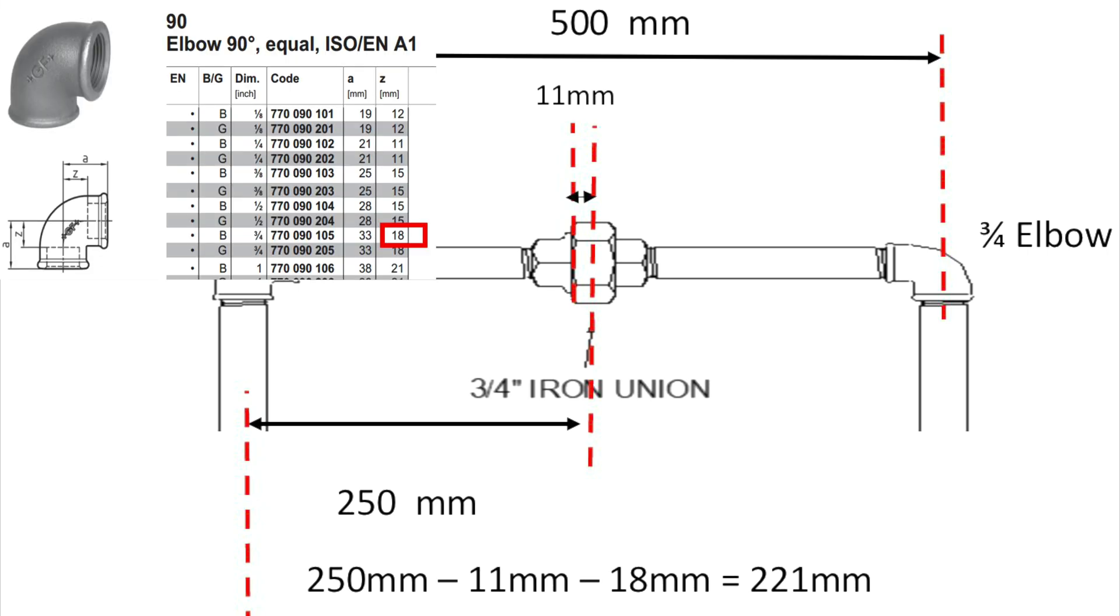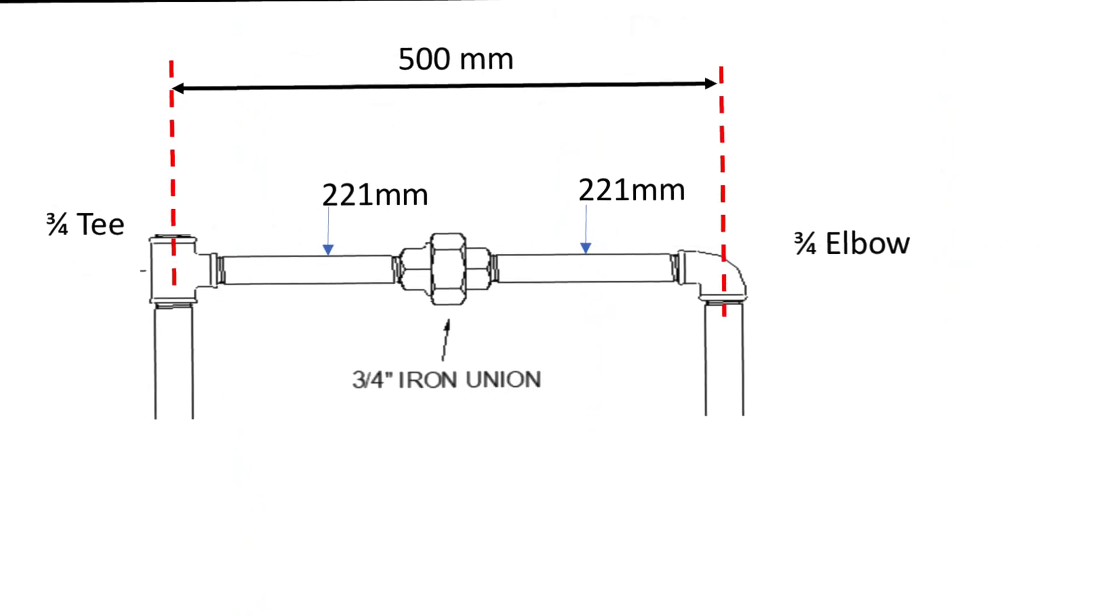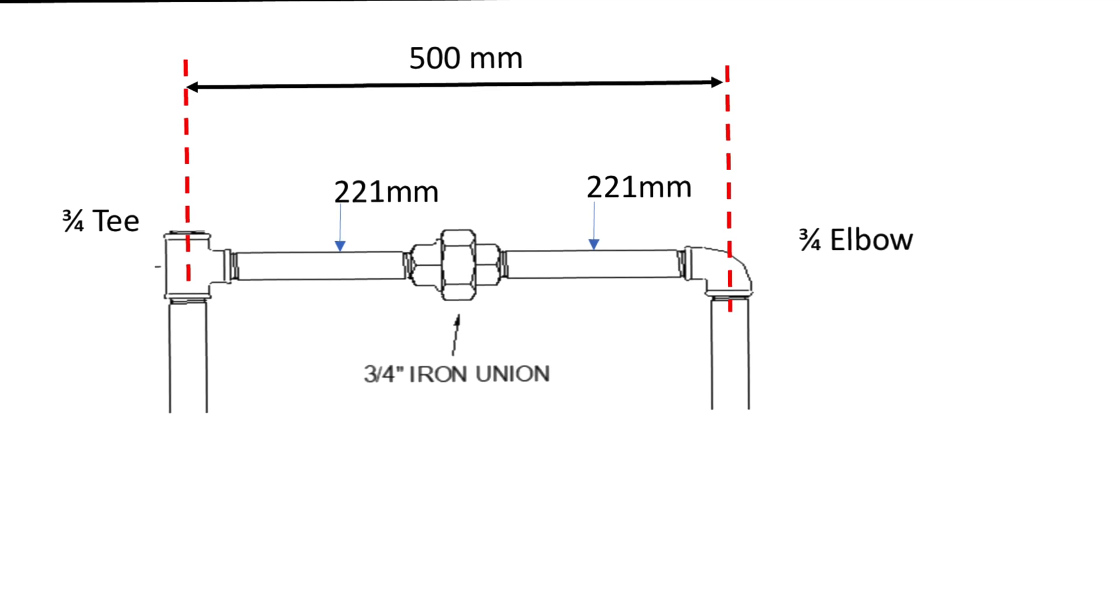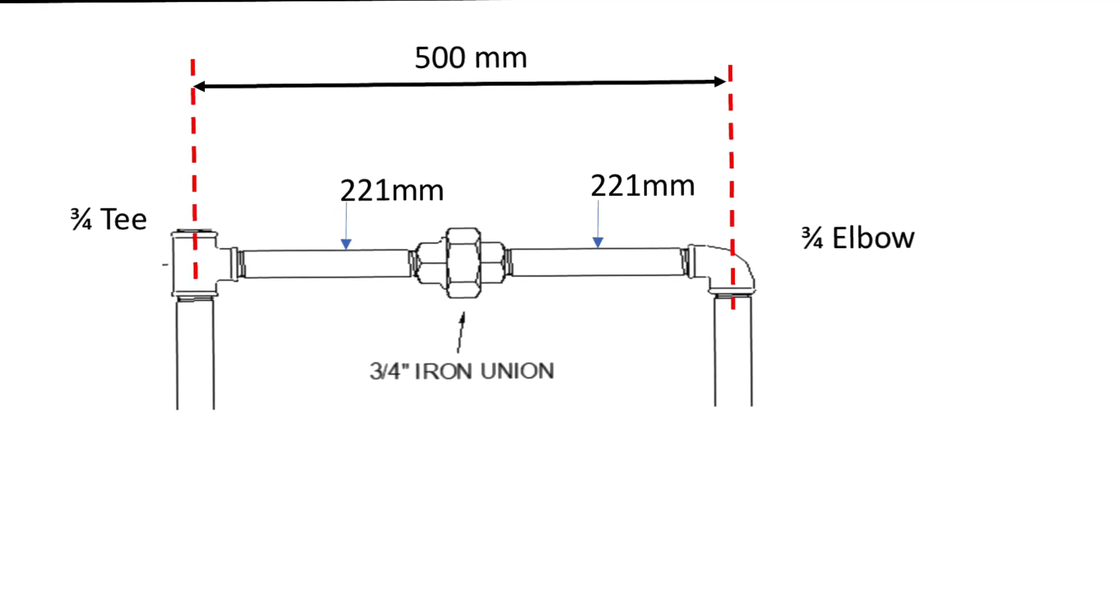Luckily, the elbow has the same Z dimension, so that is also going to be 221mm per side. So we cut each pipe 221mm to give us a 500mm centre to centre.